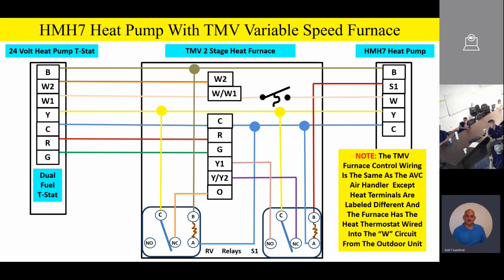Now the TMV furnace, please note something: the wiring is the same as the AVC air handler, except the heating terminals are labeled a little bit differently. And the furnace has that little heating thermostat wired into the W circuit from the outdoor unit. So the only difference between the wiring schematics is that little switch on the furnace product, on the W/W1, and please remember you also have to be sure to have a dual fuel thermostat. So let's go ahead and watch this.